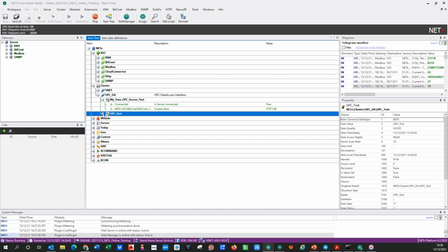You have a LonWorks installation, and normally it's updated up to BACnet. But if it's an old installation and the customer is not interested in spending money to convert to BACnet, maybe they use a typical OPC server from LonWorks to OPC. OPC DA or even OPC UA is also a different possibility. But we will deal with OPC in the future.